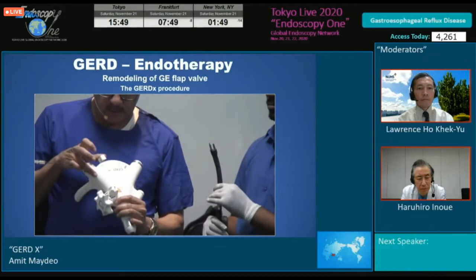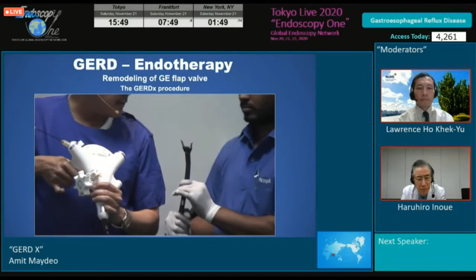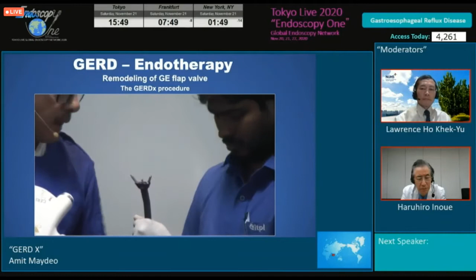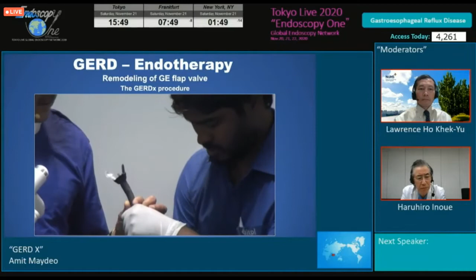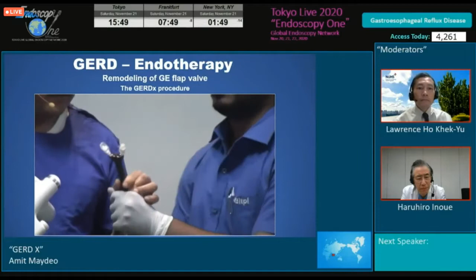So first, before applying the staple, we have to move this lever in the open position by pushing it ahead and then turning it towards the right. And then by pressing this handle, we can open the two arms at the distal end of the GERDx device. Once this is opened, we are going to apply the staples, which are disposable. So on one side is the receiving end of the staple, which has got the plastic pledget, whereas on this side is the actual staple itself, which has got these two needles to which this thread is attached.